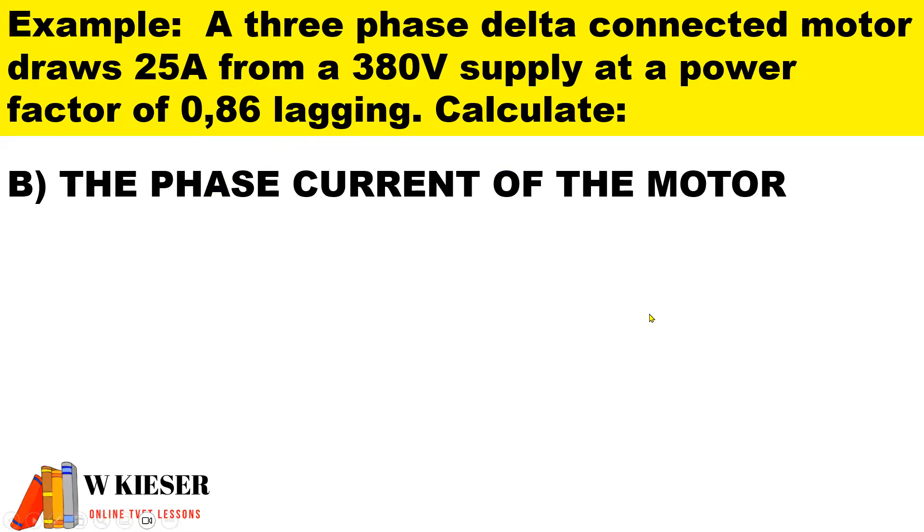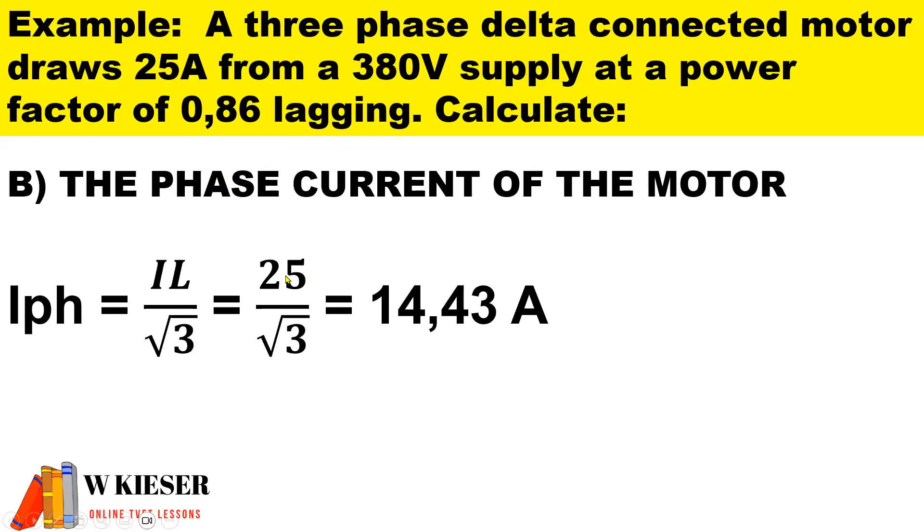To calculate the phase current of the motor, I phase is equal to IL divided by square root 3 because it's a delta connected motor. And so therefore we get 14.43 amps.